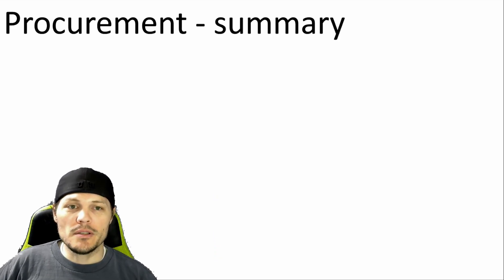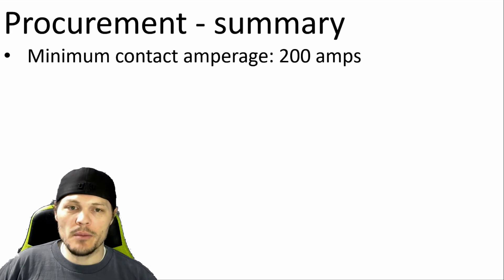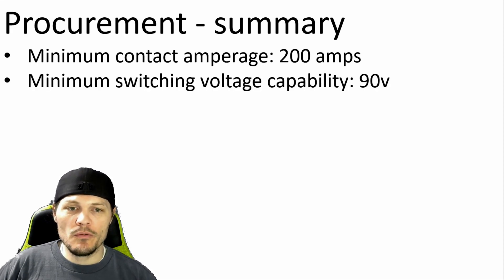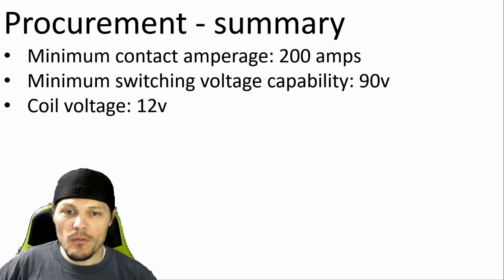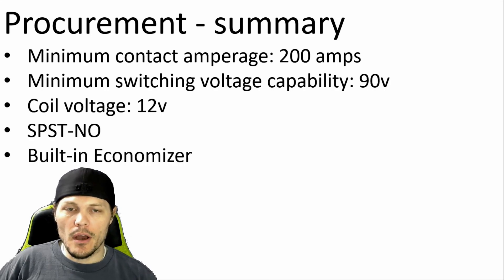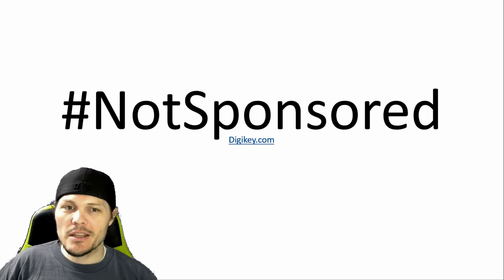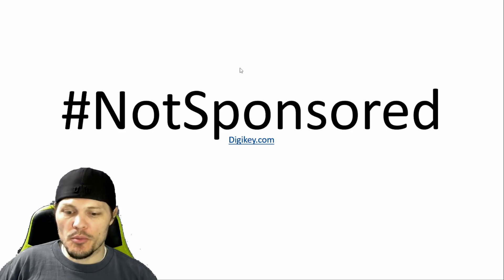So to summarize, I want my contactor to have the following characteristics: a minimum contact amperage of 200 amps, a minimum switching voltage capability of 90 volts, coil voltage of 12 volts, single pole, single throw, normally open, and a built-in economizer. DigiKey.com is a website that sells all sorts of electronics for industry and has a pretty good product filtration system. So let's head over to that website and punch in our parameters.